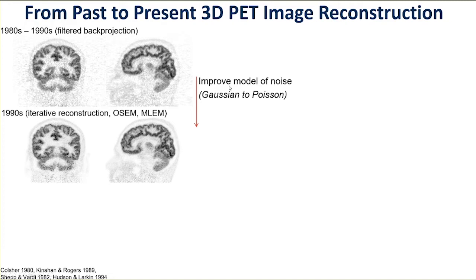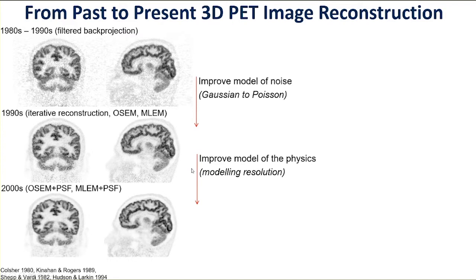If we upgrade to the iterative procedure, we change from the Gaussian model implicit in filtered back projection to a Poisson noise model — and iterative reconstruction, ordered subsets EM or maximum likelihood EM, notably reduces noise especially in low-activity regions. Furthermore, we can not only improve the noise model but also the model of the physics. In PET imaging, a successful technique was to build in modelling of the positron range or point spread function, improving the spatial resolution of images. That takes us to about year 2000.